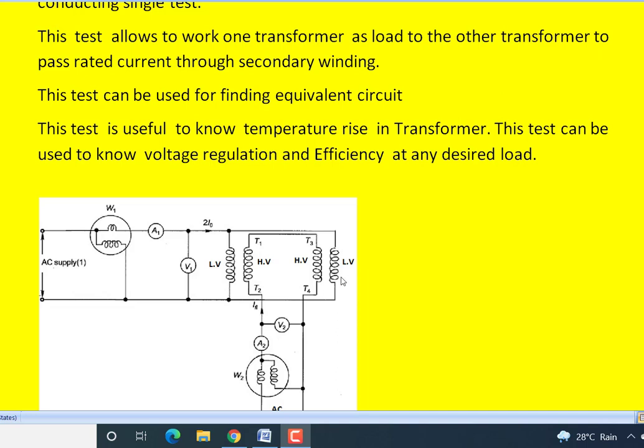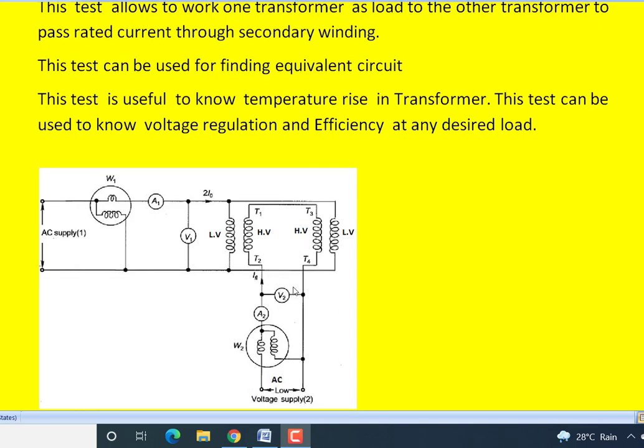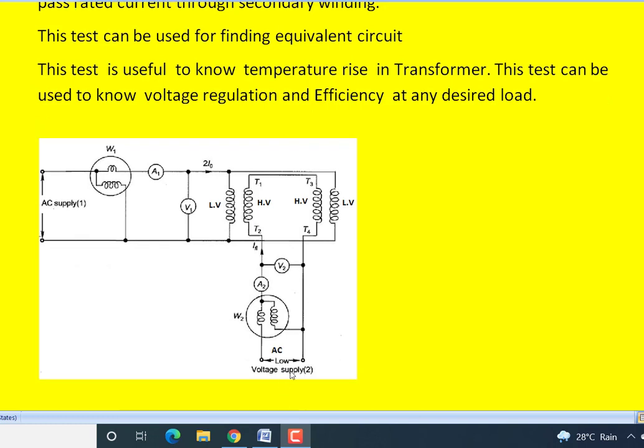So if you look closely, the primary windings are LV windings, meaning low voltage rating windings. They are connected in parallel, and that parallel connection is connected across the AC supply via a voltmeter, ammeter and a wattmeter like this. Then here we have the secondary windings and they are connected in series like this. Their connection should be in series opposition, and these windings will be connected to a low value, variable AC voltage through a voltmeter, ammeter and a wattmeter.